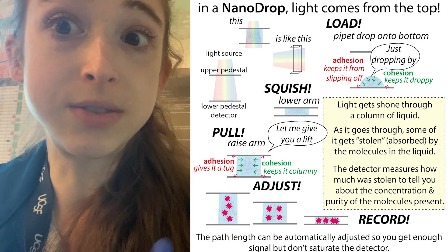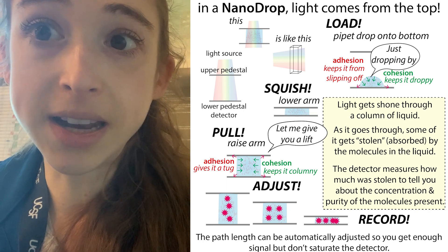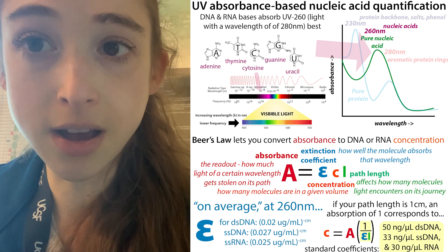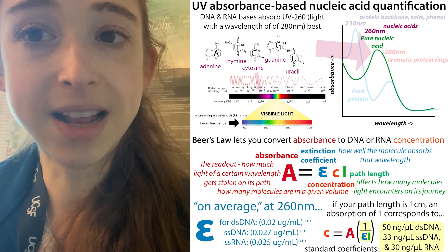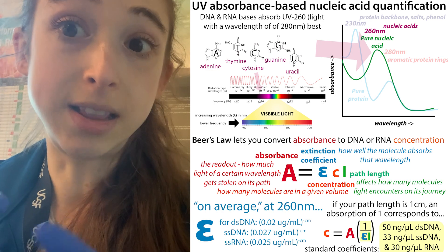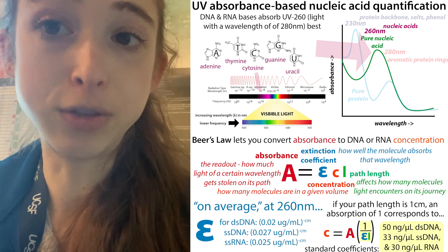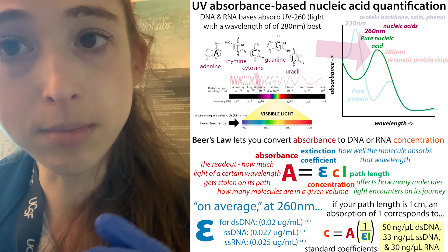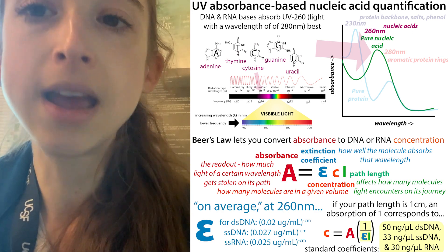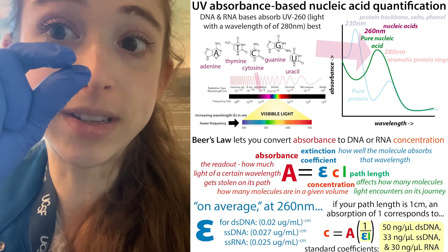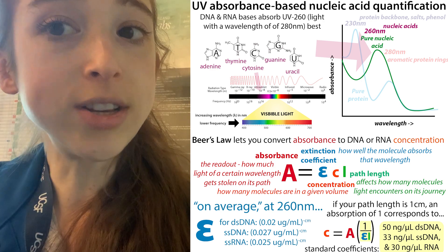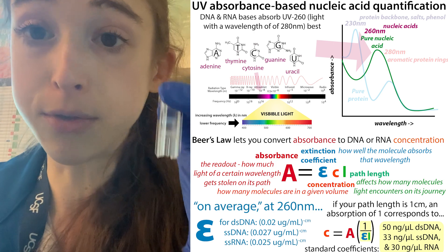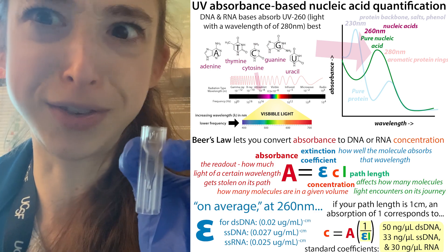The nanodrop has this variable path length, which could make things complicated if you tried to calculate concentration directly from Beer's Law. But the nice thing about the nanodrop is it actually converts the path length in its software, showing you the absorbance as if the path length were one centimeter - the typical standard length, which is the same as 10 millimeters. So even though the actual path length is smaller, it adjusts and reads out as if taken from a normal cuvette spectrophotometer.